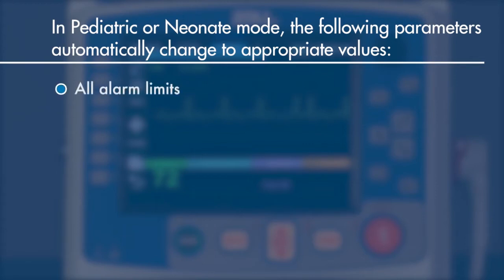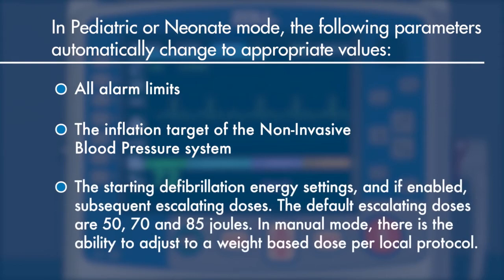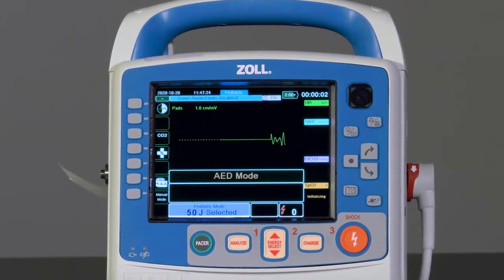When the X-Series Advanced enters either pediatric or neonate mode, the following parameters are changed automatically to age-appropriate values: all alarm limits, the inflation target of the non-invasive blood pressure system, the starting defibrillation energy settings, and if enabled, subsequent escalating doses. The default escalating doses are 50, 70, and 85 joules. In manual mode, there is the ability to adjust to a weight-based dose per local protocol.